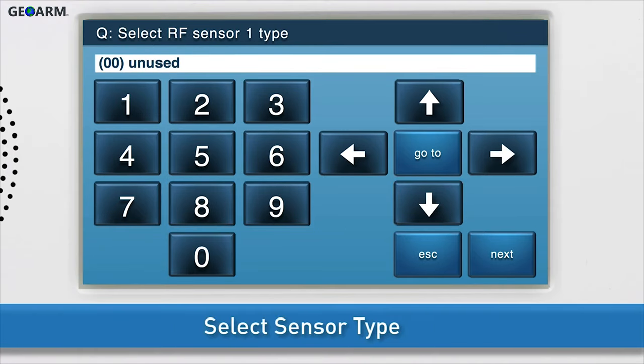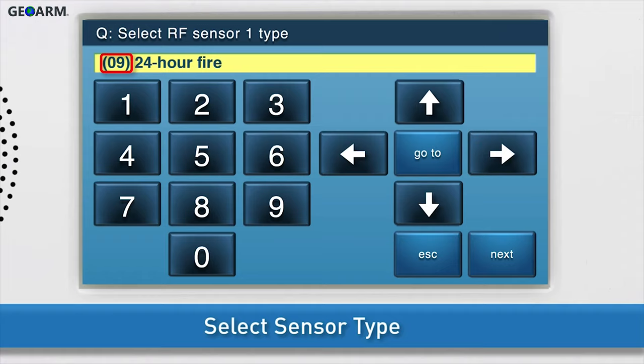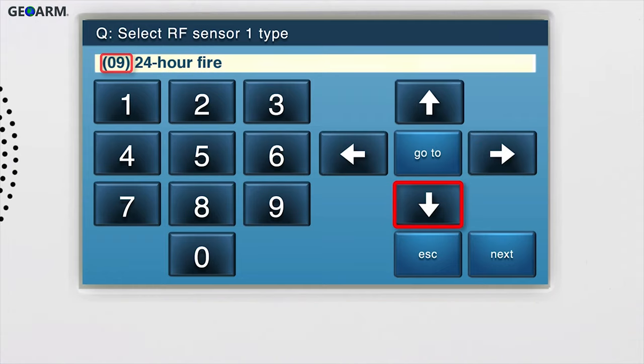Select the sensor type. There are two ways to change the sensor type. Option 1: Press the right arrow until 24-hour fire displays on screen. Option 2: Use the on-screen keypad to type 0, 9, which is the two-digit code for the 24-hour fire sensor type. Press the down arrow to go to the next sub-question.